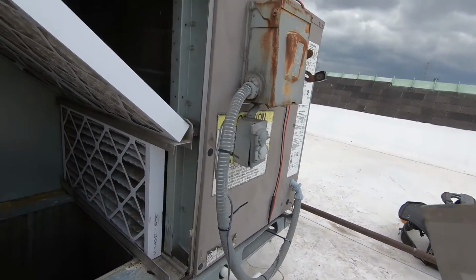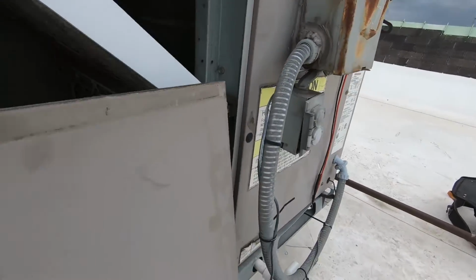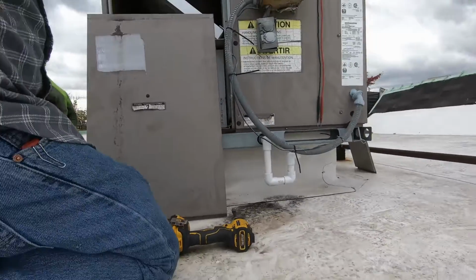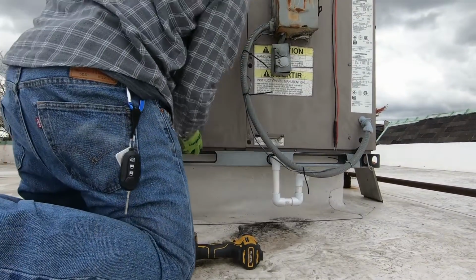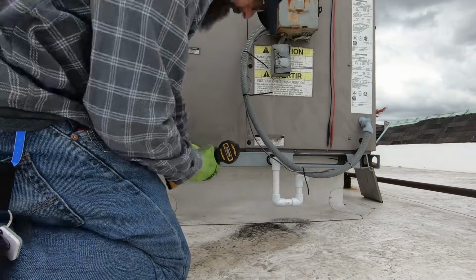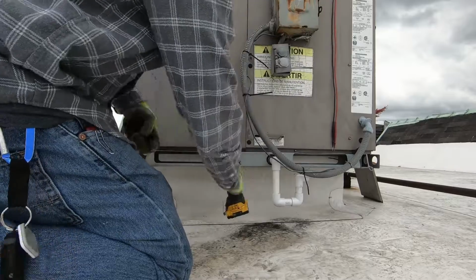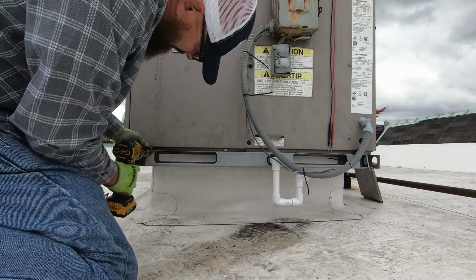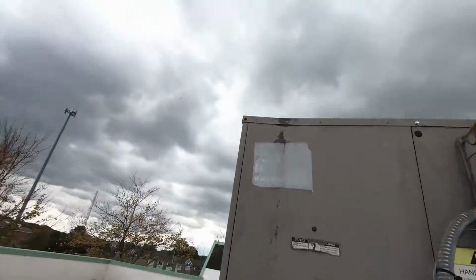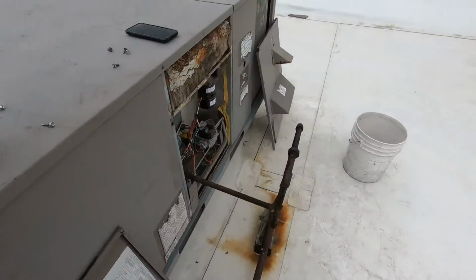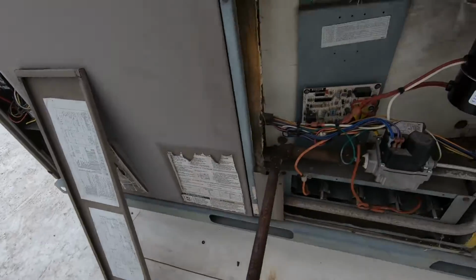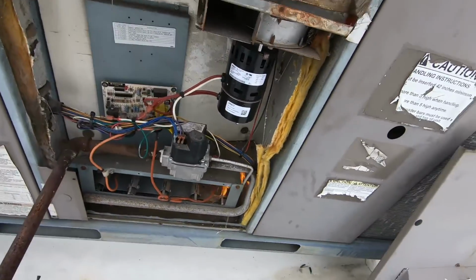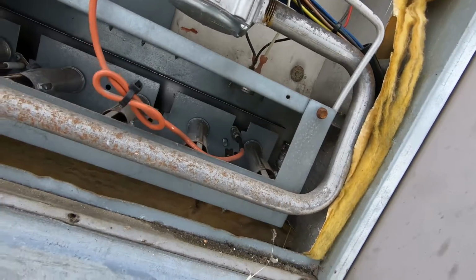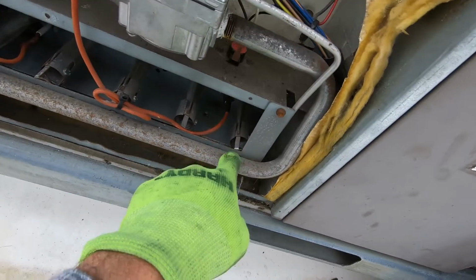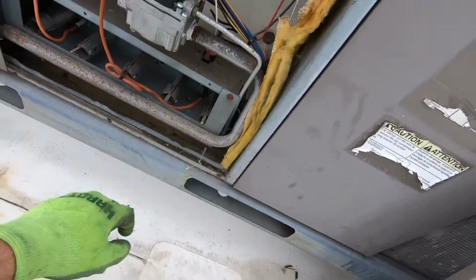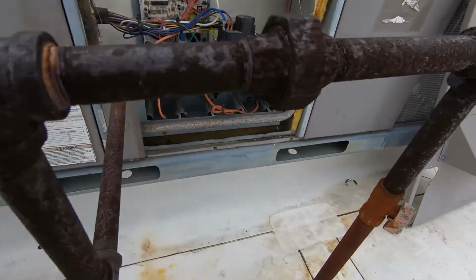All right, now I'm gonna reset power. Wait for the time delay on the thermostat. All right, she lit up already. Blower's running. Oh, and we're rolling out. See that? Why are we rolling out? I bet you we got something plugging up this burner or plugging up that orifice.